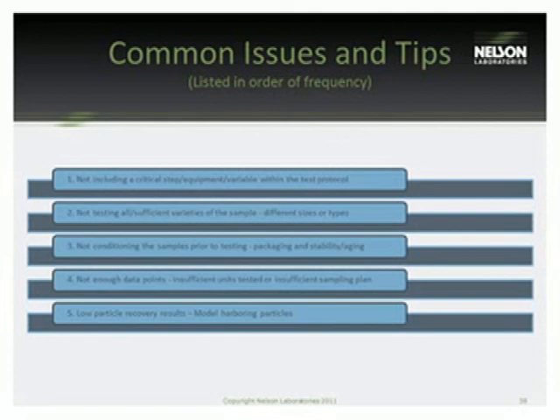Definitely a good idea. Not conditioning the samples prior to testing. This includes packaging and stability or aging. In many cases, we've seen where our clients have not done sterility prior to testing, and that's had a hang-up with the FDA. We found that sterility rarely impacts particulate matter, but the FDA just likes to see it. It can have an impact, depending on what sterility method is used. Heat can sometimes have a higher impact than, say, EO, but they like to see a final product because they want to see what's going to be subjected to the patient, and that's understandable.